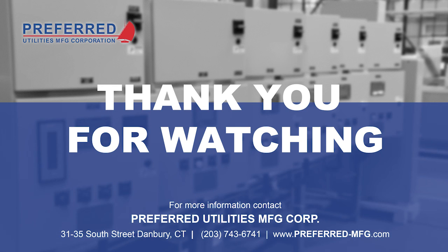Next question. I think there's only a couple more. When routing from an outside filling pump station into a building up to a rooftop belly tank, does that piping need to be containment pipe with leak detection? The rule of thumb is if that piping is going to go through an occupied space, you're going to need to have double wall pipe. And in most places, we will put a leak detector at the bottom of the interstitial of that double wall pipe, and an alarm if that leak detector goes off.